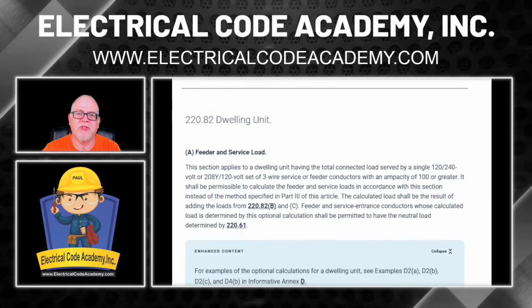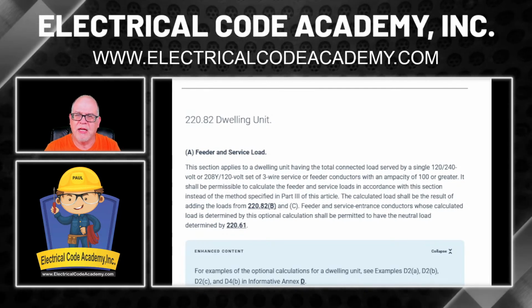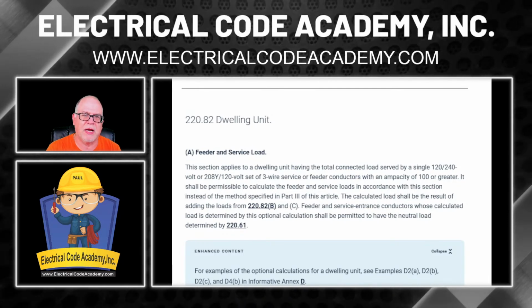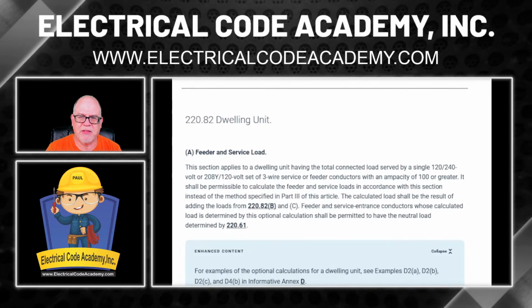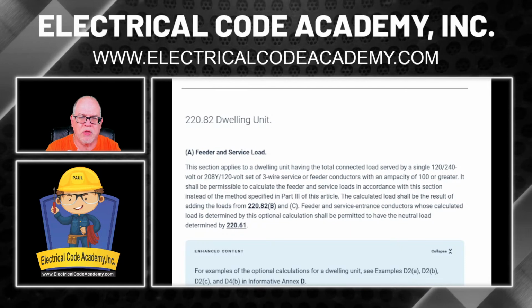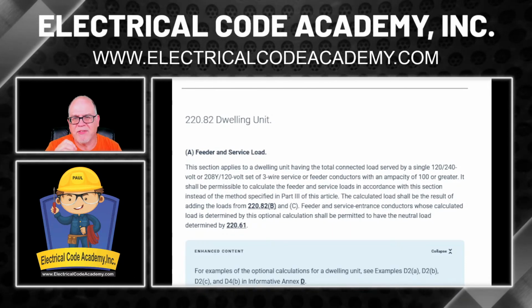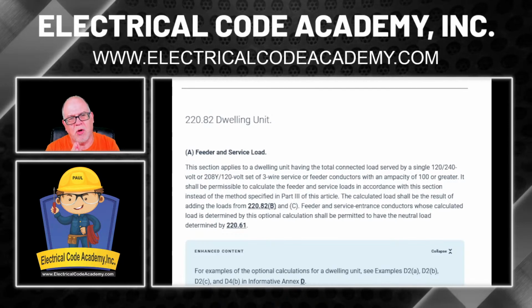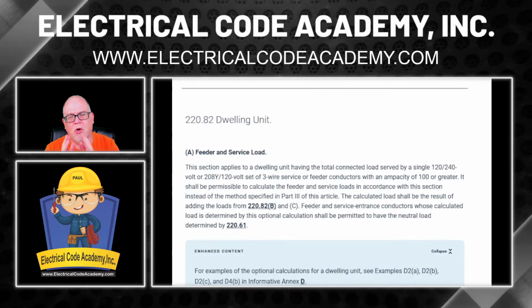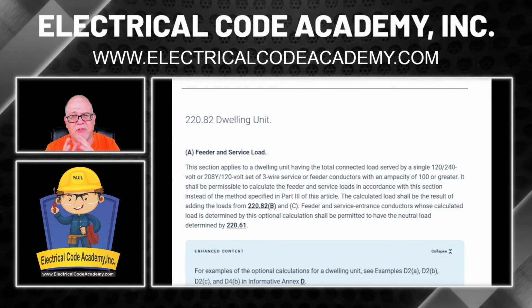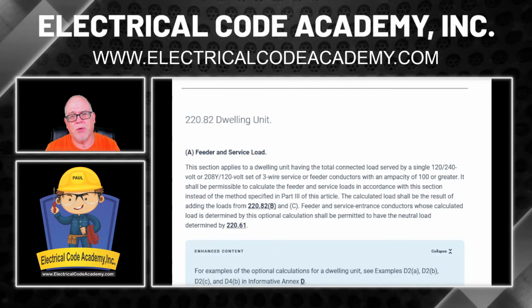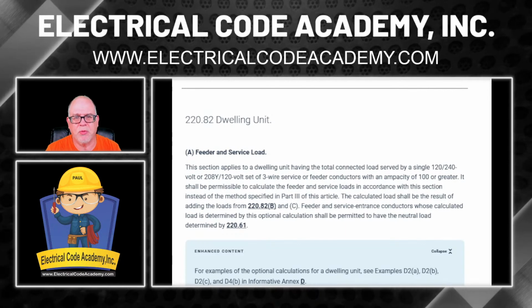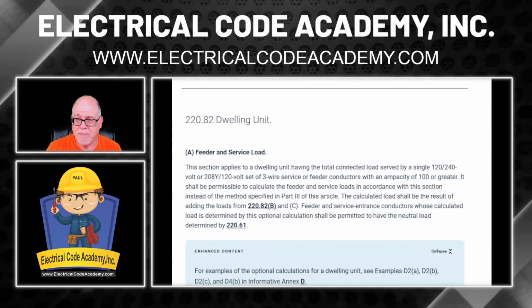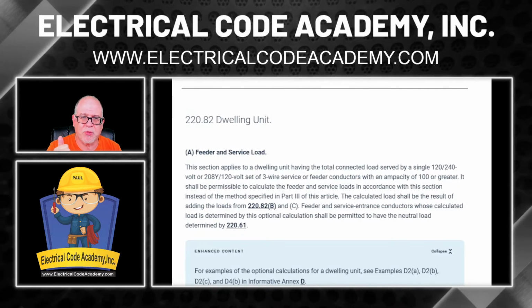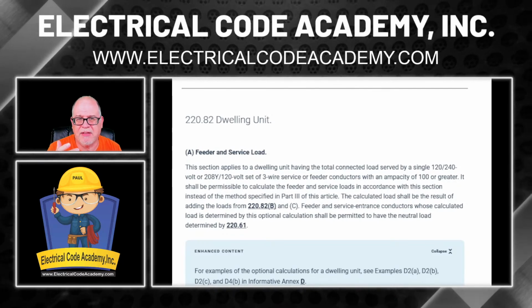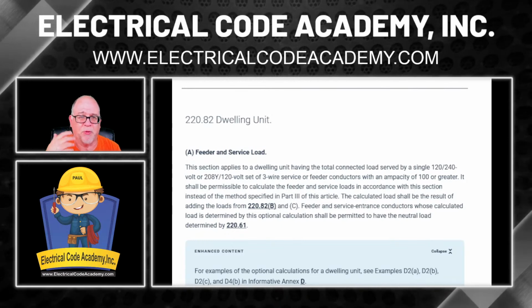All right. So what you see is it talks about feeder and service loads, and it tells us that since it's a dwelling unit, we're going to follow this optional method if it's a 120/240 or a 208Y/120. Well, even though it was 230 and 115, we know that the nominals are 120/240. So we know that we're dealing with a single phase 120/240. But that's not the most important part here. This is broken down into an A, a B, and a C. B is going to be the one that deals with the 3 VA per square foot, talks about adding up all the nameplates, the first 10,000 at 100% and the remainder at 40%.